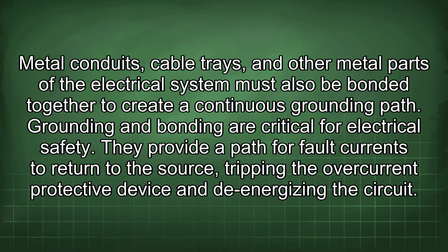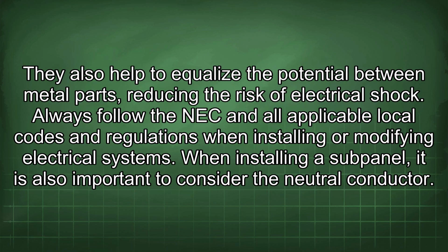Metal conduits, cable trays, and other metal parts of the electrical system must also be bonded together to create a continuous grounding path. Grounding and bonding are critical for electrical safety. They provide a path for fault currents to return to the source, tripping the overcurrent protective device and de-energizing the circuit. They also help to equalize the potential between metal parts, reducing the risk of electrical shock. Always follow the NEC and all applicable local codes and regulations when installing or modifying electrical systems.